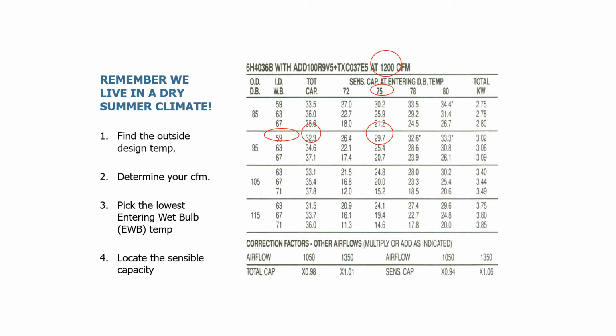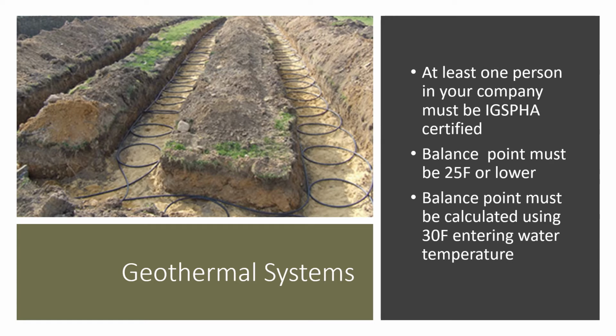And if for whatever reason you wanted to go to a humid climate, say it's all the way up to 67, your sensible capacity would be actually less than a 2-ton machine, roughly at 21,000 BTUs. A little word about geothermal. At least one person in your company needs to be IGSPHA certified. We'd like to see a balance point of 25 degrees or lower. And here's the important part: when you're doing the calculations, the balance point must be calculated in incoming water temperature of 30 and not 50. There's a reason we put antifreeze in the loop, because it does get cold and might freeze. And by the end of winter, in most systems we've inspected, the incoming water is close to freezing, not below freezing.